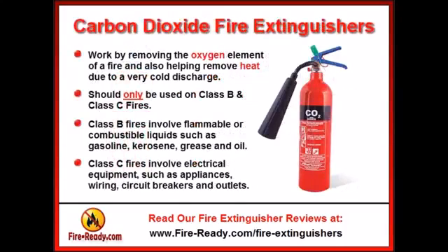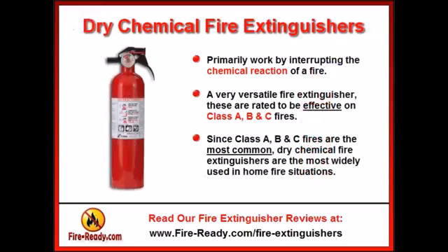Carbon dioxide fire extinguishers work by removing the oxygen element of a fire and also helping remove heat due to a very cold discharge. Carbon dioxide fire extinguishers should only be used on Class B combustible liquid fires and Class C electrical fires. Dry chemical fire extinguishers primarily work by interrupting the chemical reaction of a fire. A very versatile fire extinguisher, these are rated to be effective on Class A, B, and C fires.